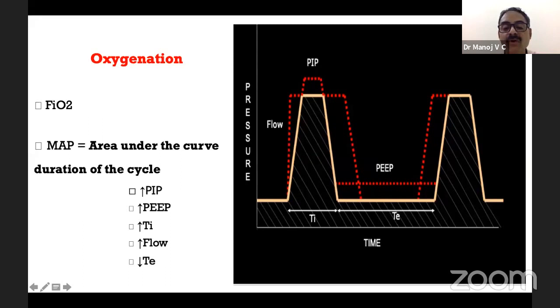If you increase the flow from a sine wave, your pressure waveform will become a square wave. I am introducing two terms now, sine wave and square wave. If the flow is very fast, high flow, the peak pressure is reached very, very fast. So increasing the flow will convert a sine wave to a square wave, and will increase the area under the curve.